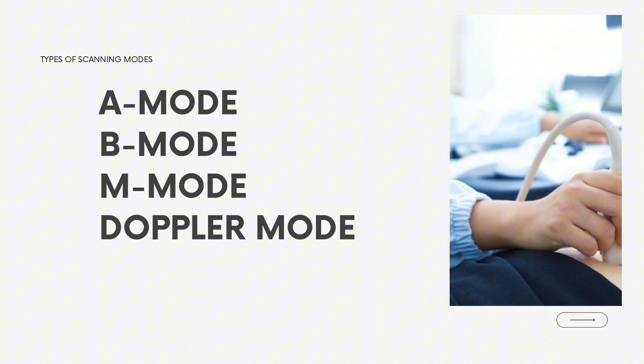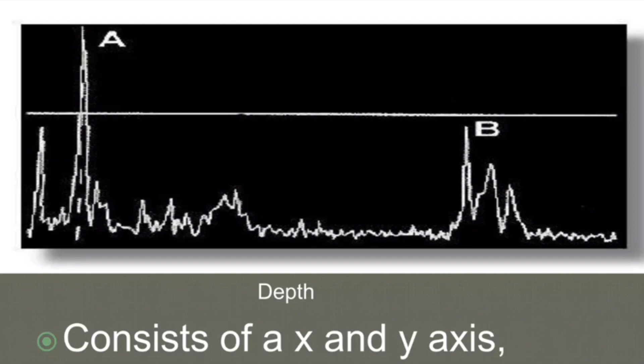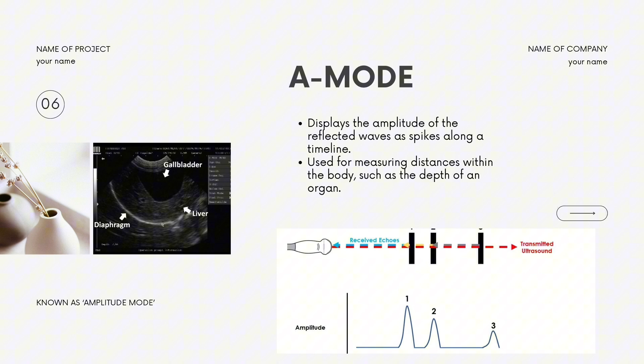What is A mode? A mode, which is amplitude modulation, is the display of amplitude spikes of different heights. It represents the time required for the ultrasound beam to strike a tissue interface and return its signal to the transducer. The greater the reflection at the tissue interface, the larger the signal amplitude on the A mode screen. This graph consists of an x-axis and y-axis. X represents the depth and Y represents the amplitude. A mode can be used in ophthalmology and echocardiology. It is also used as an adjunct to B mode displays when accurate depth measurements are required.